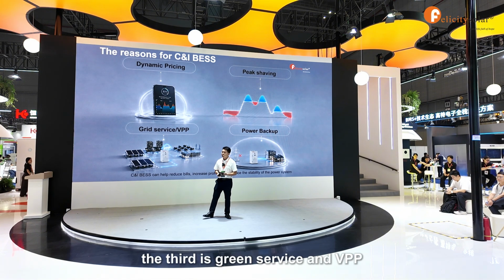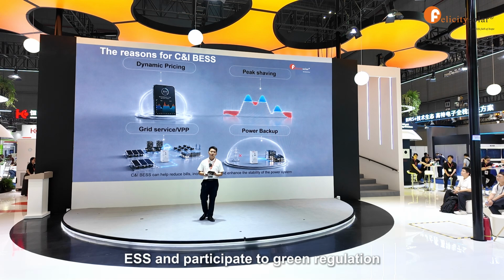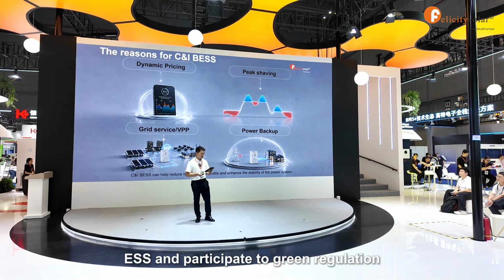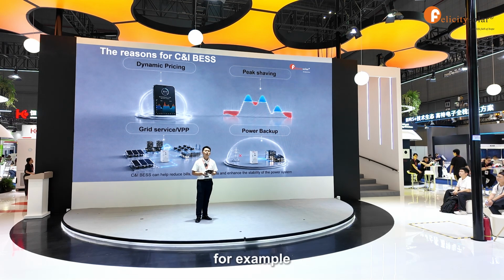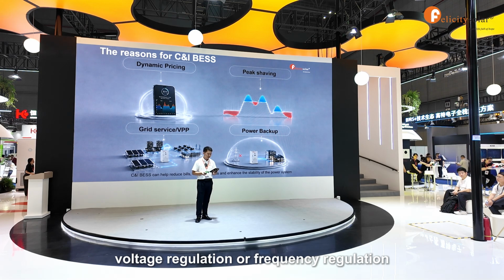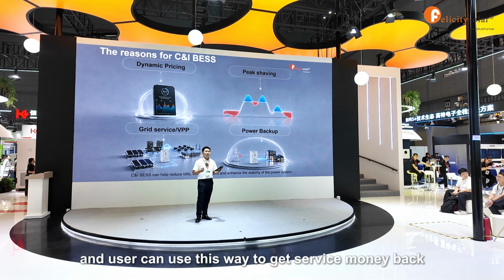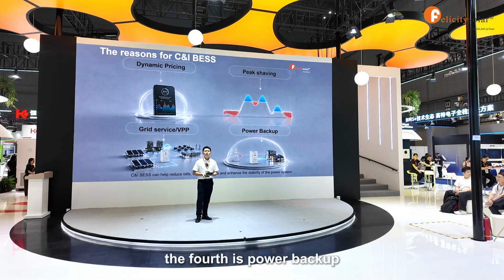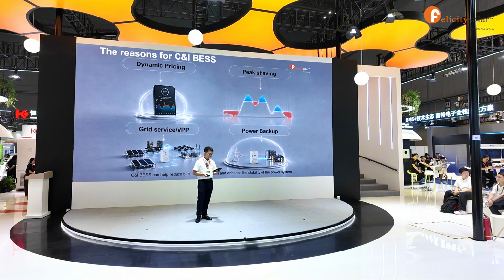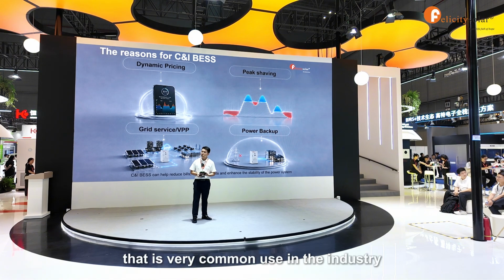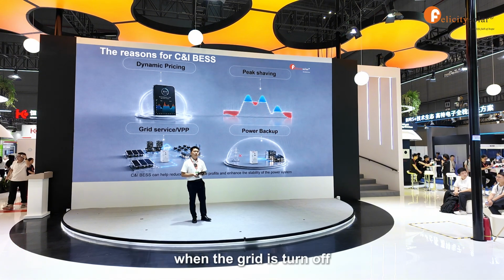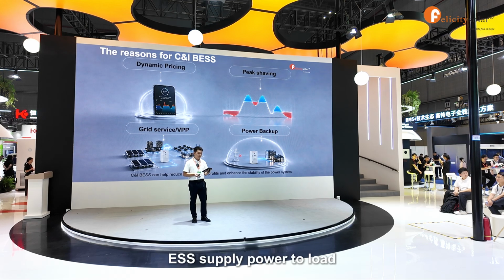The third is grid service and VPP. ESS can participate in grid regulation, for example, voltage regulation or frequency regulation. And the user can use this way to get service money back. The fourth is power backup. That is very common use in the industry. When the grid is turned off, ESS supplies power to load.